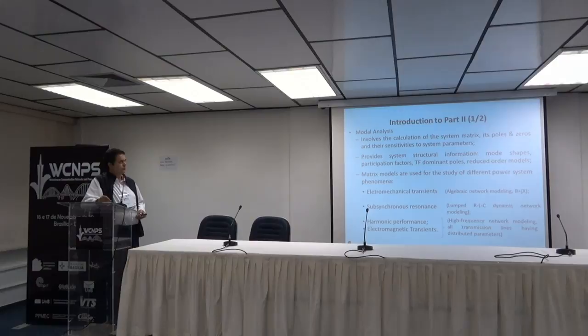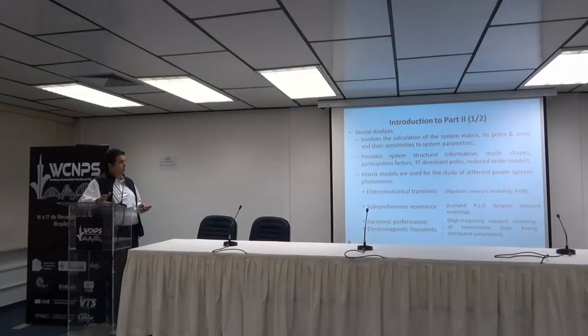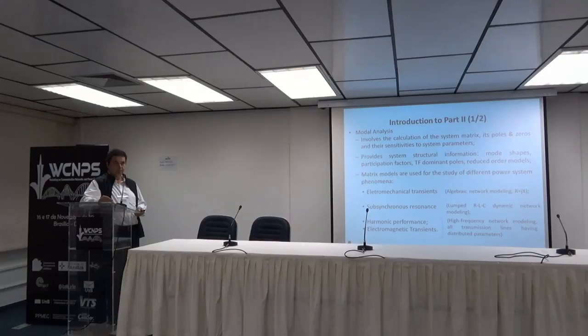I worked a major part of my life in modal analysis applied to power systems, and found the need to develop new methods to deal with large matrices and finding poles, zeros, sensitivities, mode shapes, and participation factors. When studying electromechanical transients, we use the same model as in conventional transient stability — differential equations for generating plants and associated controllers, HVDC links, etc. — but the network is expressed as algebraic equations, like in short circuit analysis, expanded into real and imaginary axes.